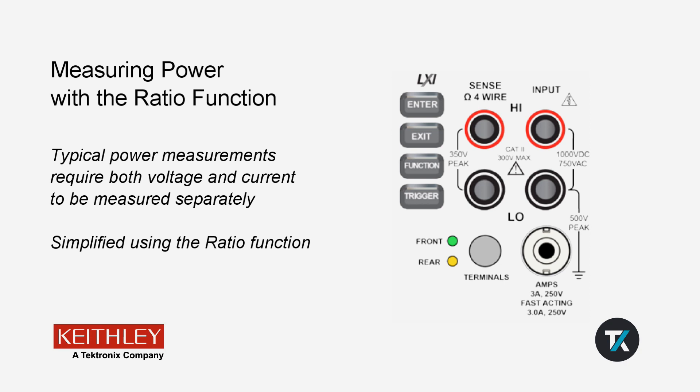Typically, this would require two separate measurements to be made, one using the input terminals and the other using the amps terminals. However, this can be simplified to a single measurement using the ratio function.